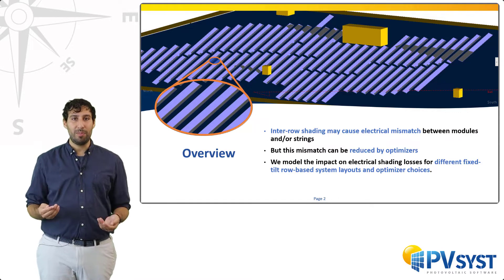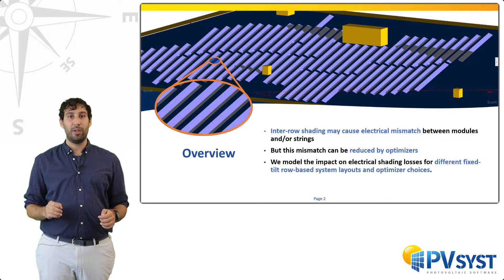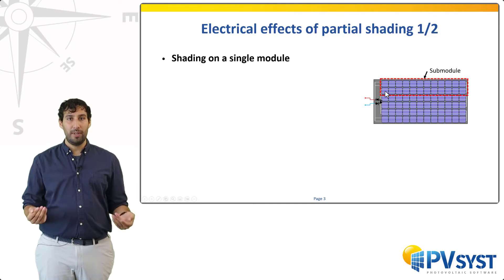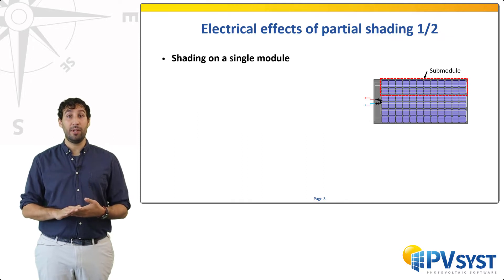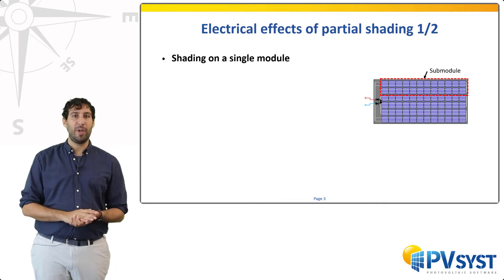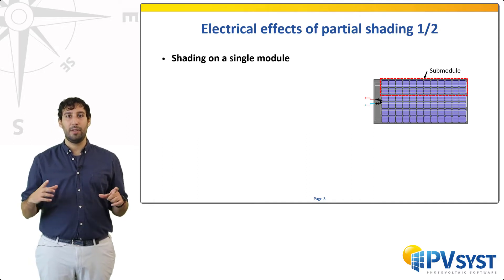Let us begin with the simplest case: the effect of shadings on a single module. The first observation is that whether one shades one cell or several cells within the same sub-module, the resulting IV curve will look roughly the same. Here, a sub-module is defined as a collection of cells in series protected by a bypass diode. This behavior is characteristic of components in series, as any current limitation will affect all components. Most of the modeling philosophy in PVSYST is therefore based on defining the fundamental unit of shading as a sub-module rather than the single cell.